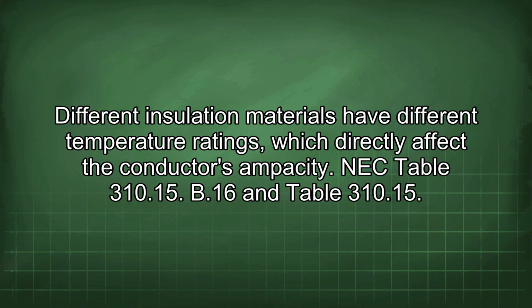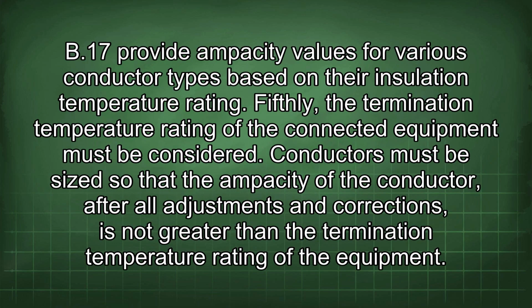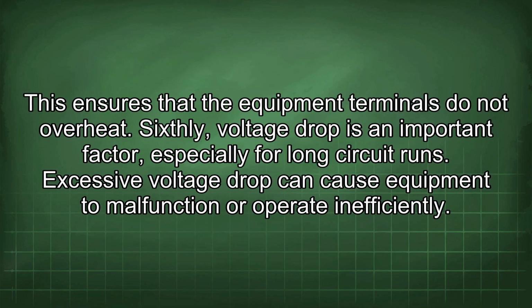Different insulation materials have different temperature ratings, which directly affect the conductor's ampacity. NEC Table 310.15(B)(16) and Table 310.15(B)(17) provide ampacity values for various conductor types based on their insulation temperature rating. Fifthly, the termination temperature rating of the connected equipment must be considered. Conductors must be sized so that the ampacity of the conductor, after all adjustments and corrections, is not greater than the termination temperature rating of the equipment. This ensures that the equipment terminals do not overheat.